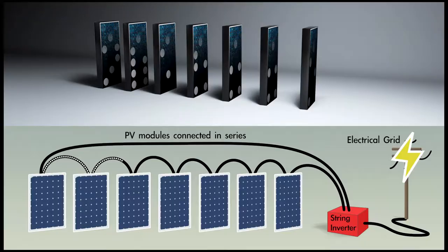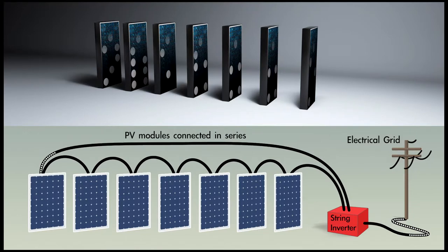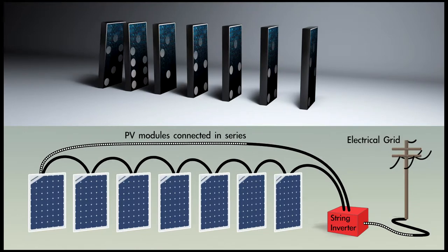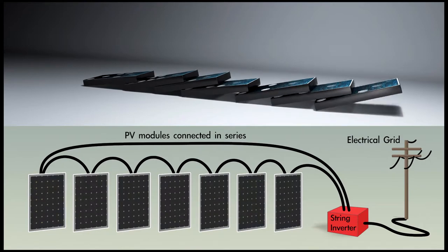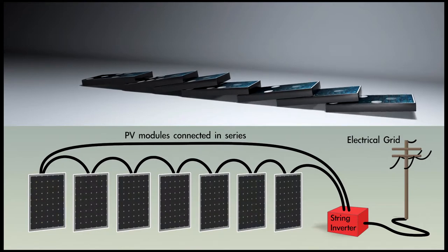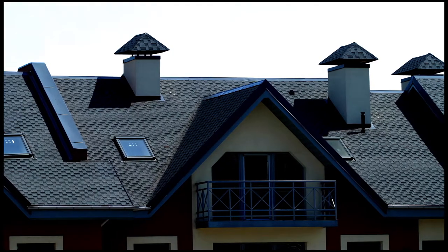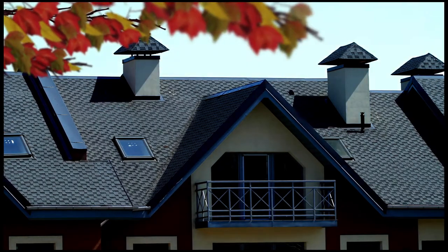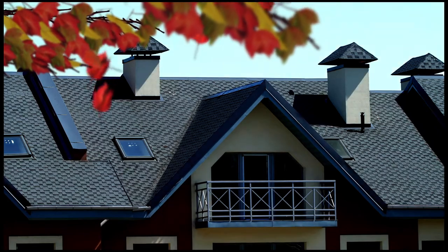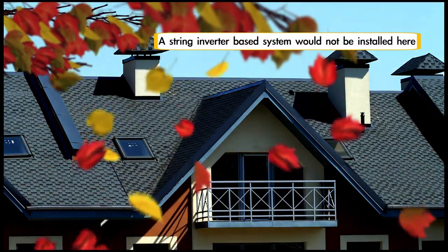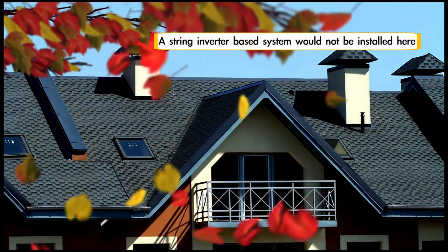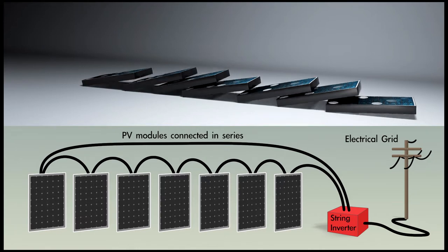The use of conventional string inverters with solar modules connected in series can degrade the performance of the entire solar PV system when any one module is partially shaded by trees, chimneys, debris, or by module variations. This creates a domino effect.